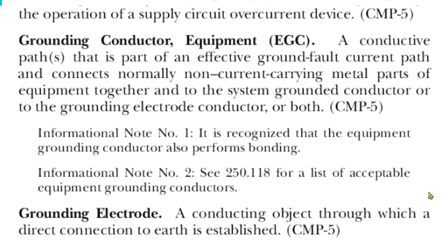Now let's move to equipment grounding conductors, or EGCs. Here's the definition of EGC found in Article 100 of the NEC: grounding conductor, equipment — that's equipment grounding conductor — a conductive path or paths that is part of an effective ground fault current path and connects normally non-current-carrying metal parts of equipment together and to the system grounded conductor. That would be your service neutral conductor, or to the grounding electrode conductor, or both. Informational note number one: it is recognized that the equipment grounding conductor also performs bonding.